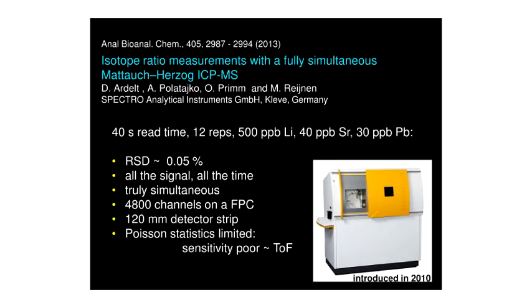This instrument is based on a focal plane camera that has 4,800 Faraday detector channels. It's relatively big — 12 centimeters in length — and therefore it can cover the full mass spectrum of the Mattauch-Herzog geometry. It provides sensitivity approximately equal to a TOF, but with improved relative standard deviation on isotope ratio precision.